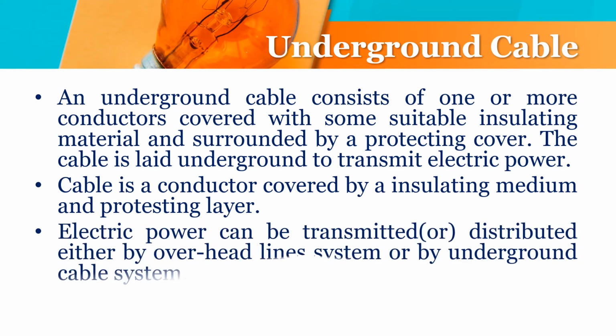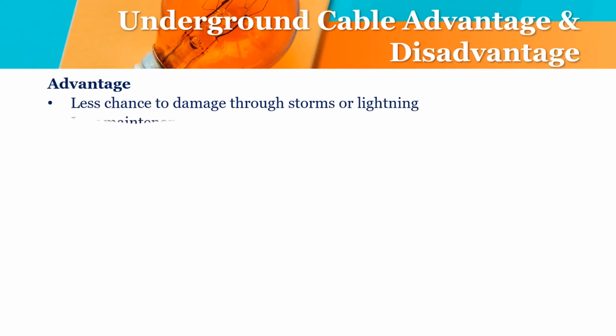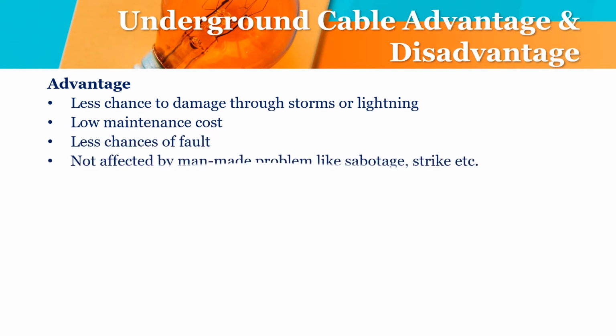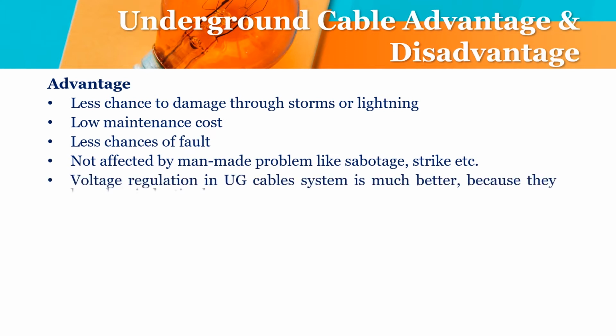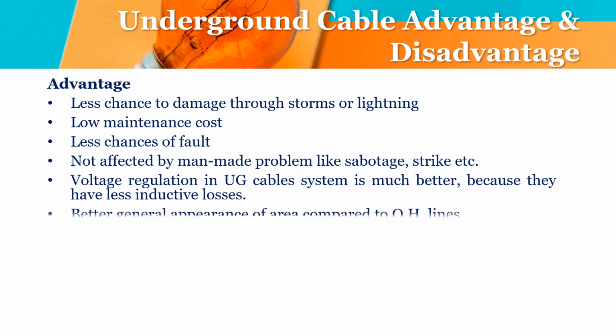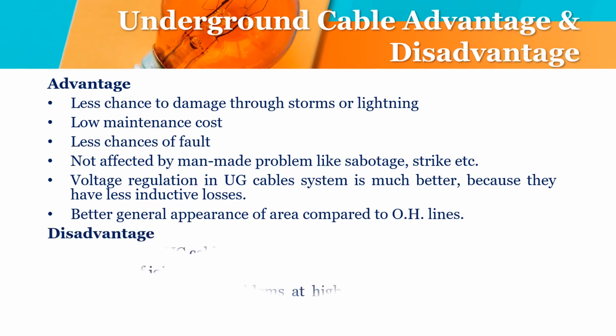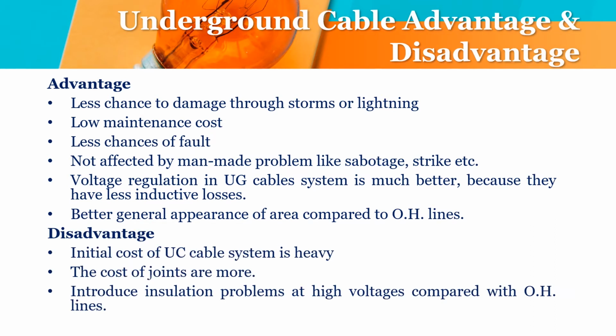Electric power can be transmitted or distributed either by overhead line system or by underground cable system. Advantages: less chance of damage through storms or lightning, low maintenance cost, fewer chances of fault, and not affected by man-made problems like sabotage, strikes, etc. Voltage regulation in the UG cable system is much better because of less inductive losses, and the general appearance of the area is better compared to OH lines. Disadvantage: the initial cost of a cable system is heavy.